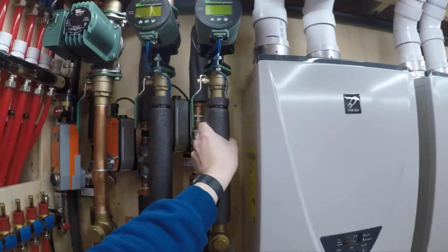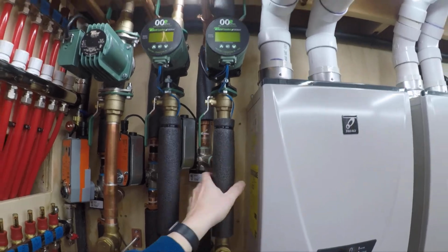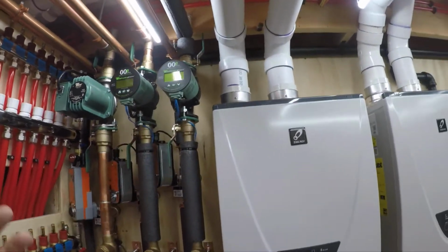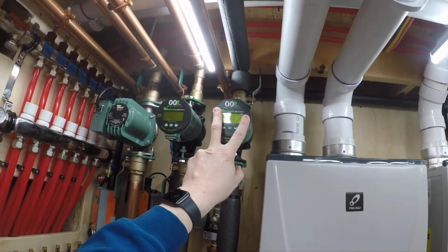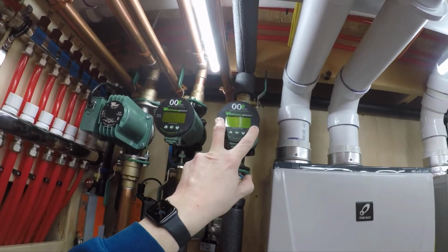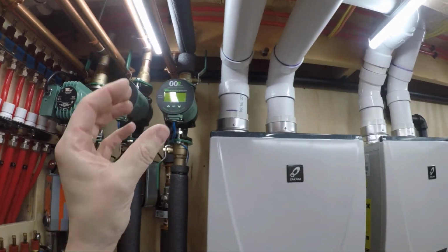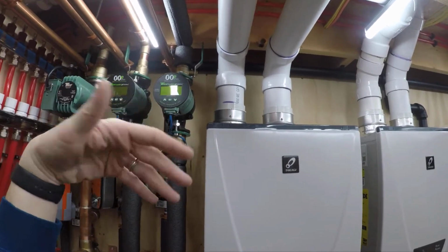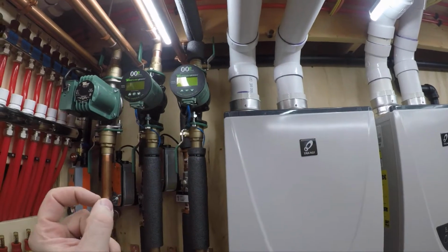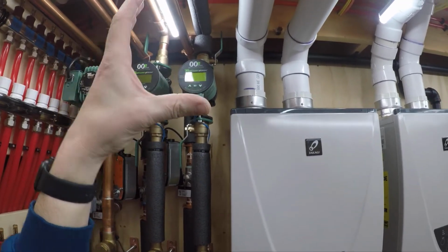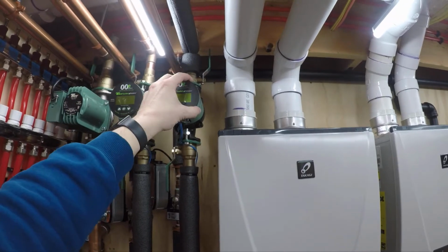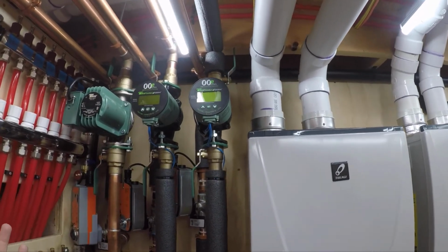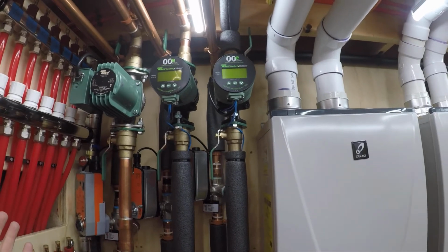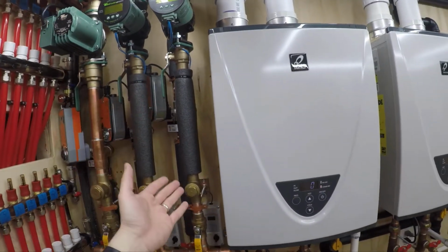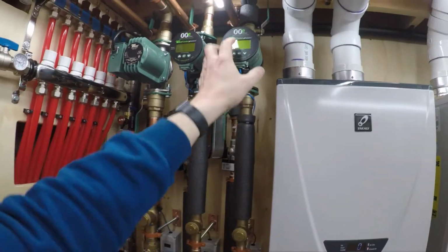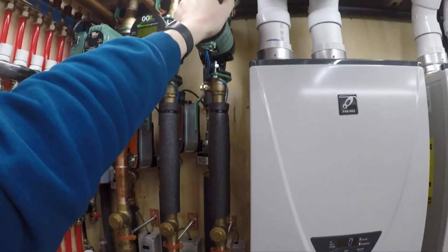So now 130 degrees is going out to the rooms, okay? These pumps will try to maintain whatever delta T you set them at. So if I have this pump set to a 10 degree delta T, it will try to keep the glycol flowing at that delta T or underneath. And as that delta T closes, the pump will actually slow down because they're ECM variable speed pumps. Very efficient.